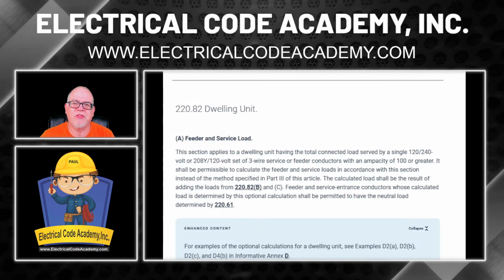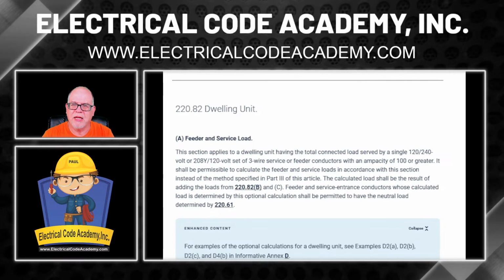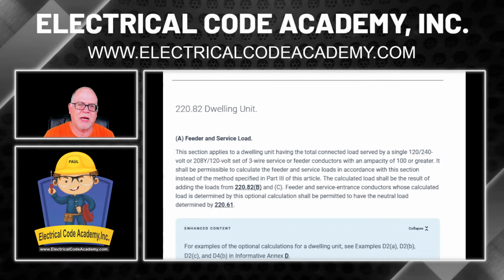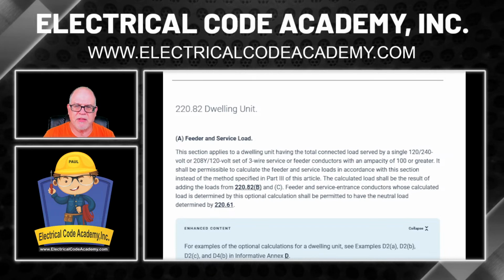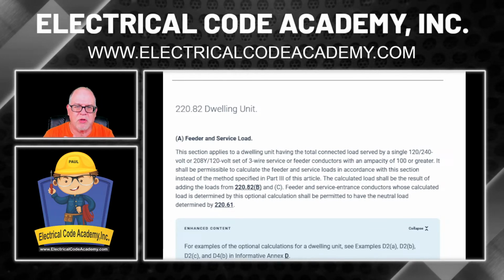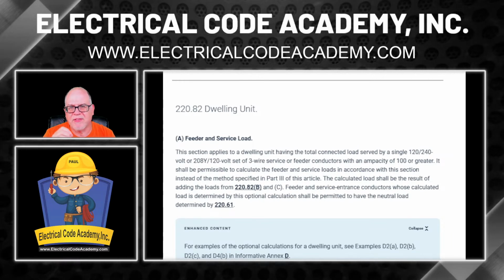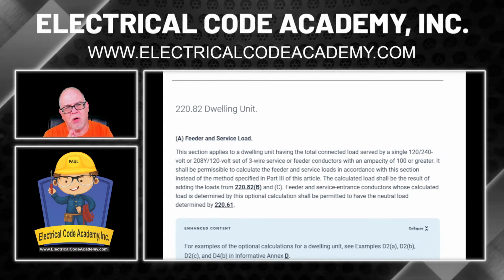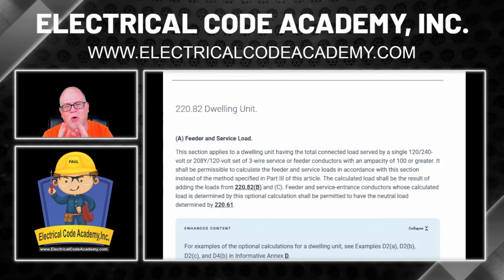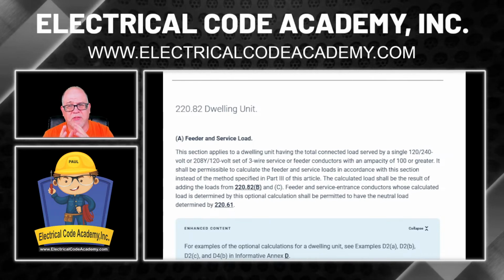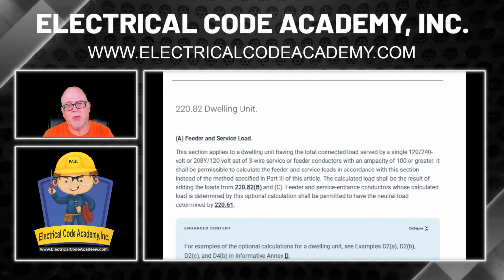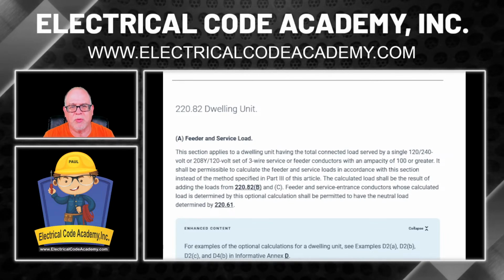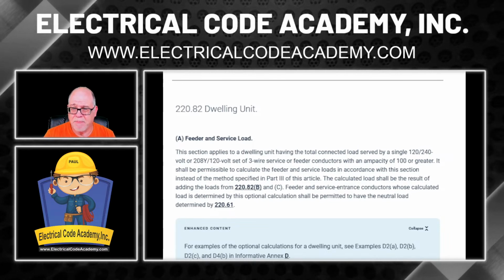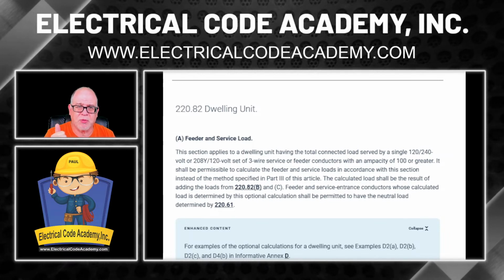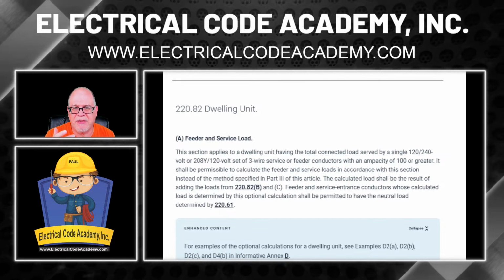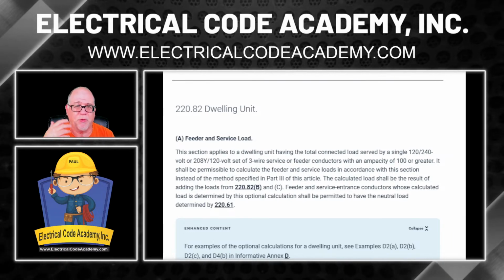All right, so what you see is it talks about feeder and service loads, and it tells us that since it's a dwelling unit, we're going to follow this optional method if it's a 120/240 or a 208Y/120. Well, even though it was 230 and 115, we know that the nominals are 120/240. So we know that we're dealing with a single phase 120/240. But that's not the most important part here. This is broken down into an A, a B, and a C. B is the one that deals with the 3 VA per square foot, talks about adding up all the nameplates, the first 10,000 at 100% and the remainder at 40%.